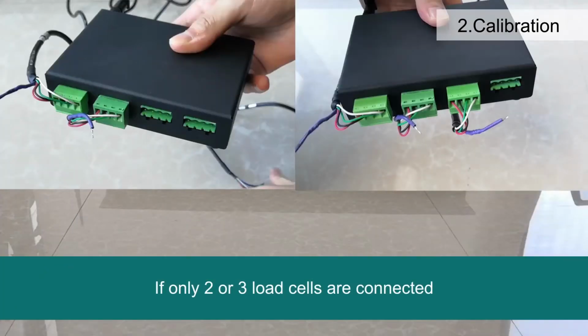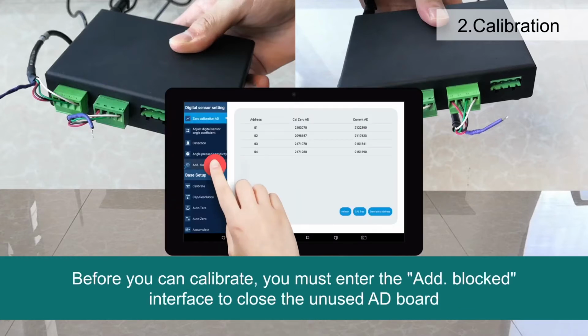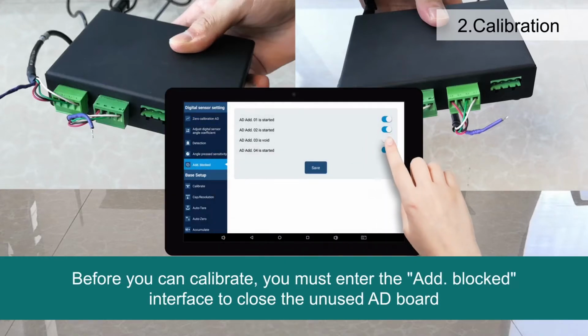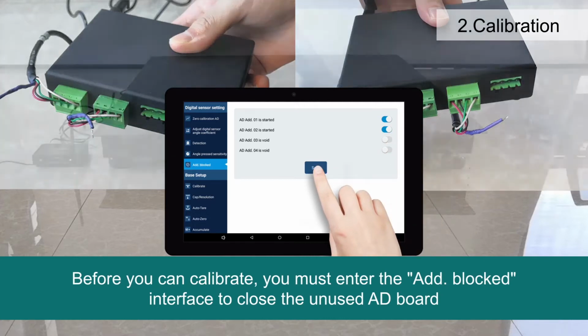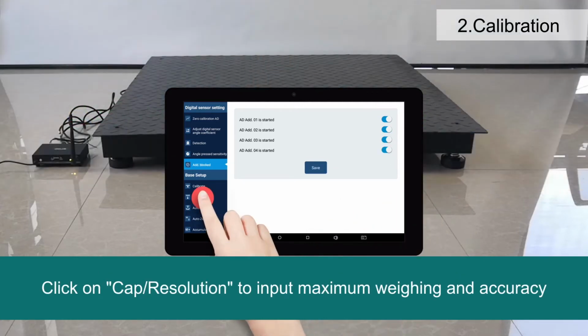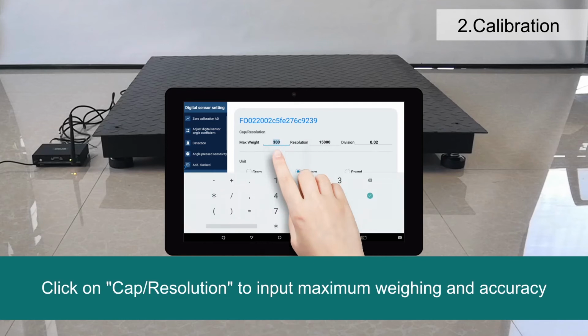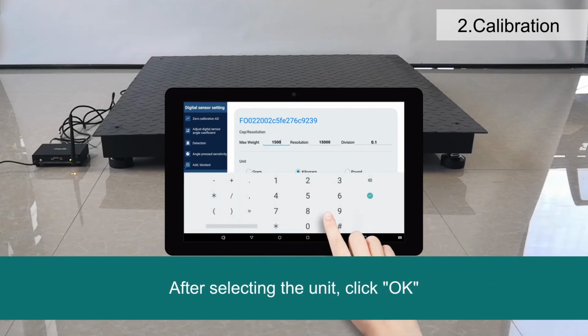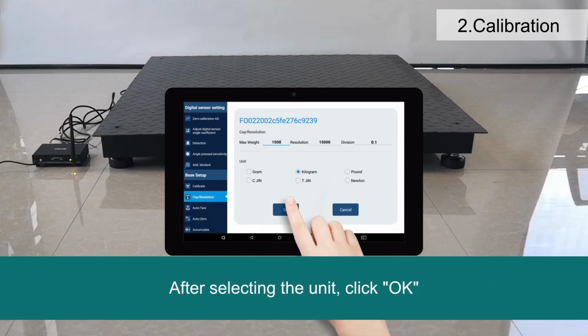2. Calibration. If only 2 or 3 load cells are connected, before you can calibrate, you must enter the add blocked interface to close the unused AD board. Click on Cap Resolution to input maximum weighing and accuracy. After selecting the unit, click OK.